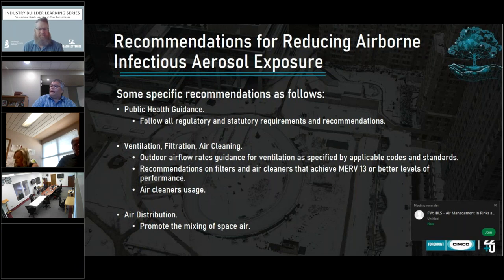You always look at outdoor air. The big acronym in the industry I came from is the solution to pollution is dilution. So the more outdoor air we can bring in, the better. The large ASHRAE recommendation on filters and air cleaners is that we want to hit a MERV 13 or better level of performance. A lot of folks out here don't understand MERV. MERV's new to them, they maybe have heard it bandied about. MERV 13 is essentially just under where we'd see a hospital. A hospital would be a MERV 14 or 15 in their ICU.